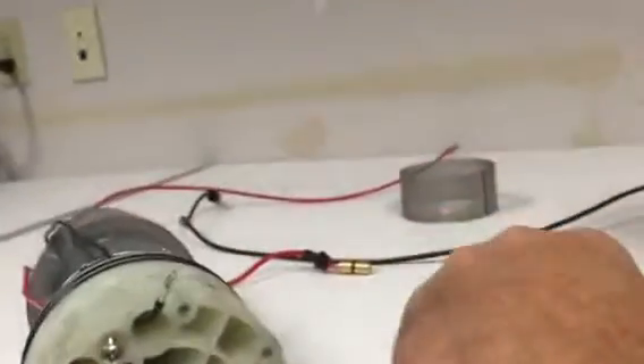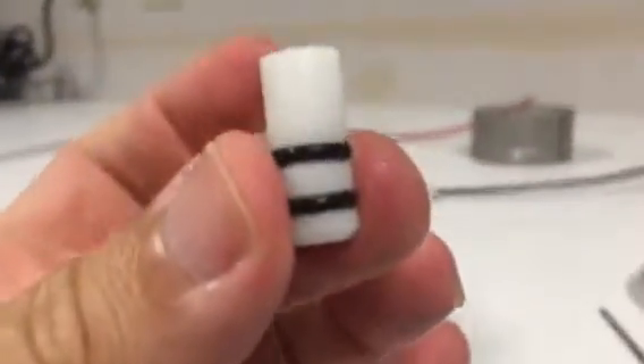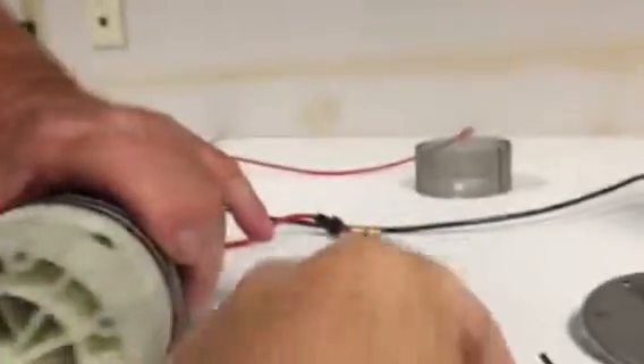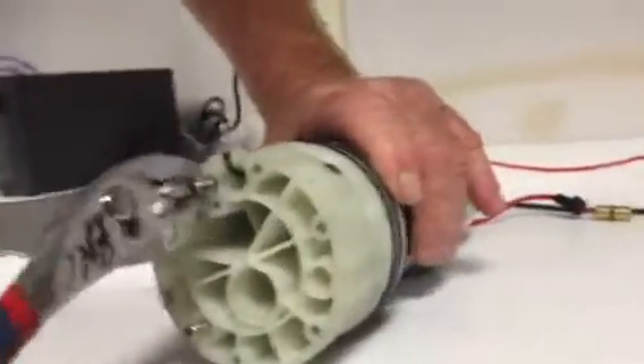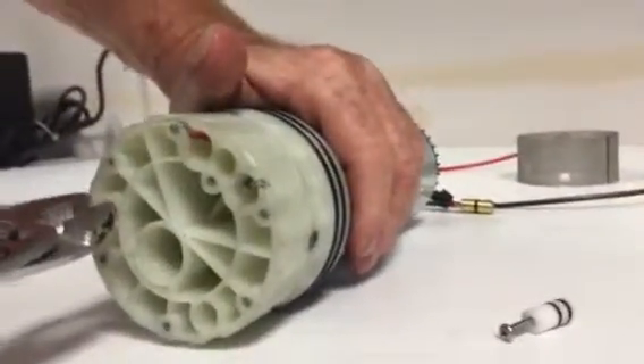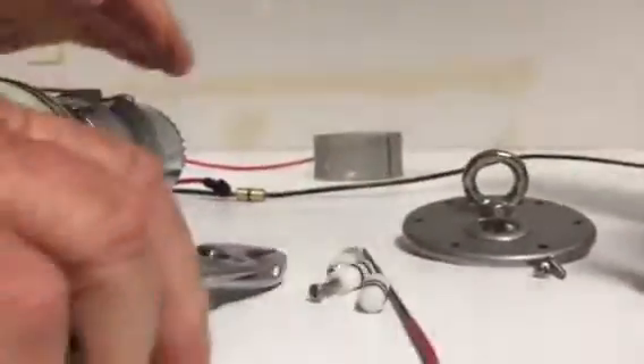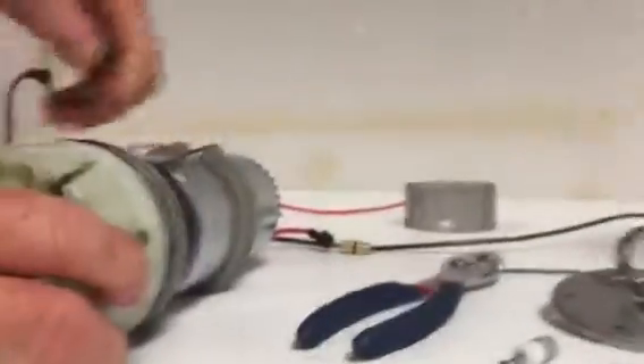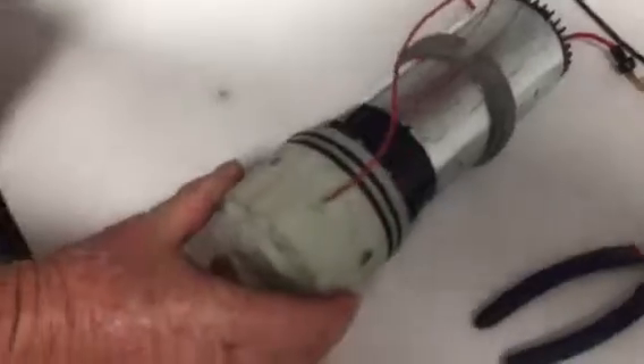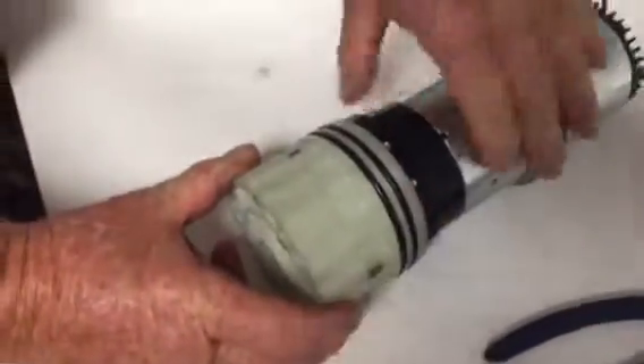There are 3 grommet pieces that need to be removed. These have a double O-ring, and these O-rings are lubricated. So ideally, with a pair of pliers, we can pull them out. Again, we can use the screws from the lid to insert lightly into this grommet piece, and that in itself can be used to pull them out. They're plugs. Once we've pulled those out, now the wires will thread out of the pump head.